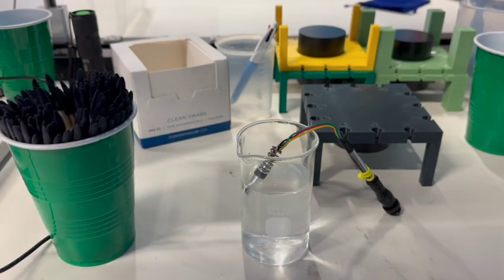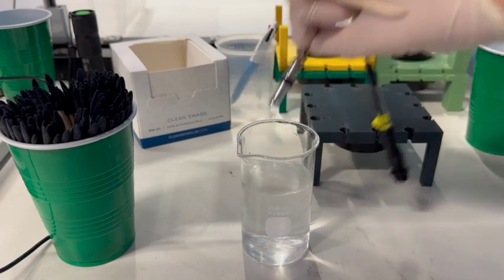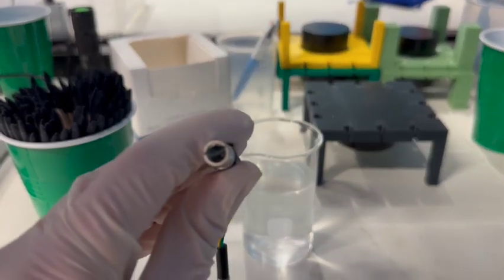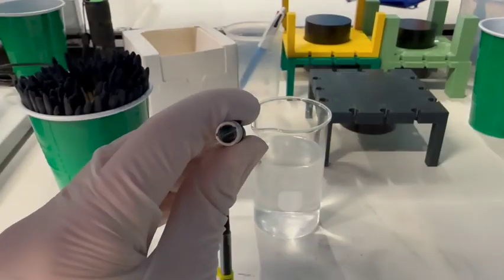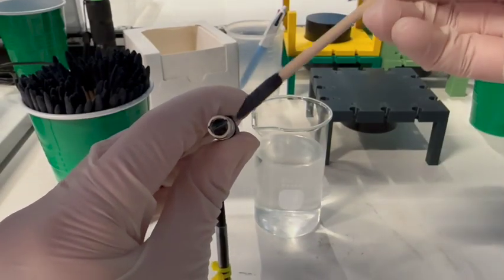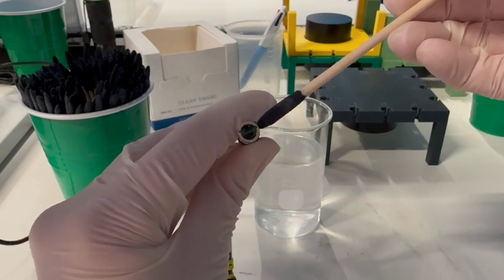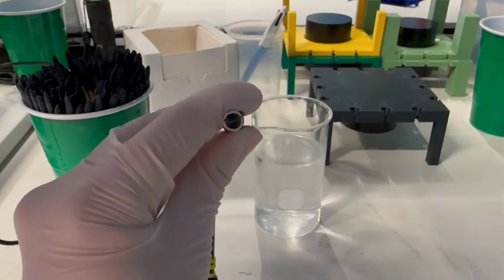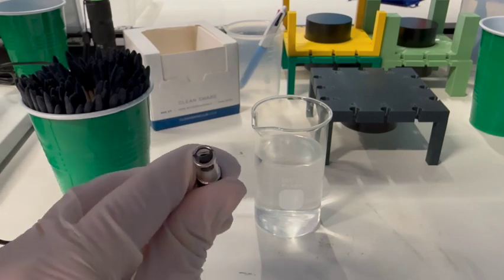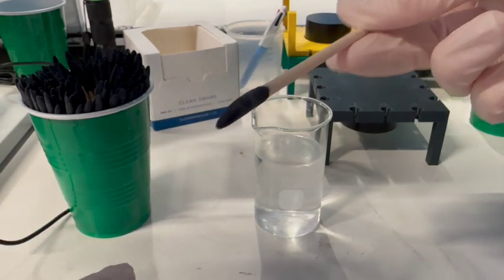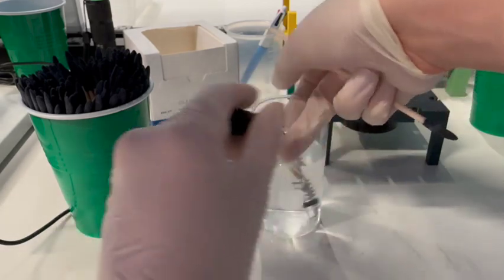All right, so I mentioned earlier, if your sensor is slow, that you can refurbish it slightly. The reason why sensors are slow is because the sensor face right here will be contaminated with anything from the plant, stuff like that. So what we can do is take a little sanding stick and lightly rub some of that contamination off.